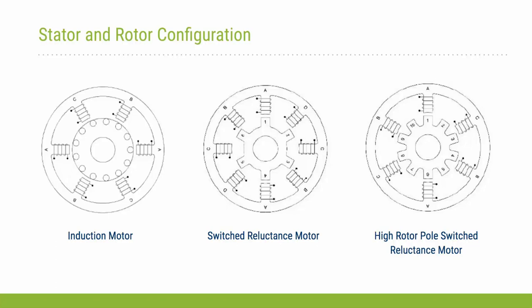Here I show a cross-section of an AC induction motor, the traditional switched reluctance motor, and the new smart motor. In the AC induction motor, a current—and hence a magnetic field—is induced in the rotor when the coils are energized, shown on the left. In the middle is the switched reluctance motor: the magnetic field generated by the energized coils passes through the rotor and forces a pair of rotor poles to line up with the poles of the coil. In that center figure, coil A has been energized, and rotor poles 1 and 4 are lining up with that energized coil.